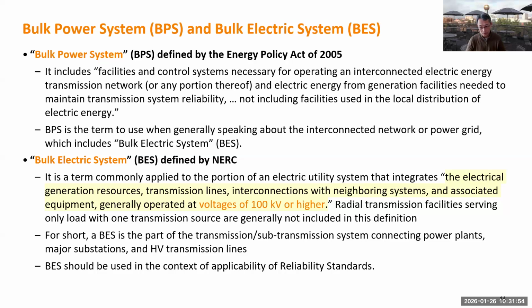When you open the system model, there will be a list of all the substations. If you pay attention to the voltage level of the substation, usually it's pretty much above 100 kV. If you see any buses with voltage like 30 kV or 20 kV, they could be a power plant, because power plants can operate at lower voltage.